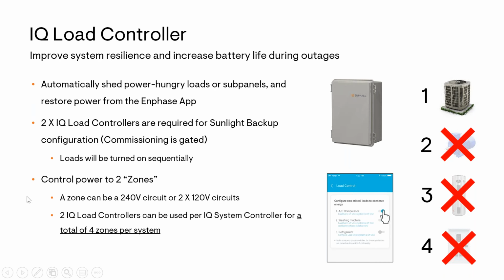Okay, a little bit more detail about what's possible with the load controllers. Each load controller can control power to 2 zones. A zone can be either a 240 volt circuit or 2 120 volt circuits. 2 IQ load controllers can be installed per system, so you would have a total of 4 zones potentially. For sunlight backup systems, 2 load controllers must be used, okay?